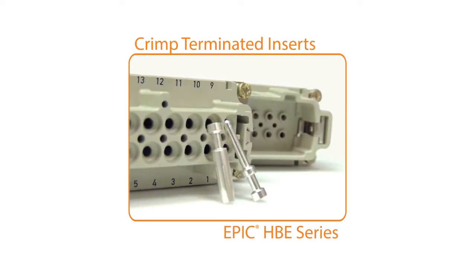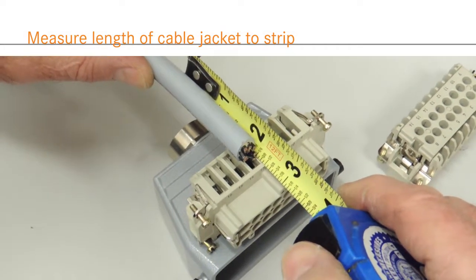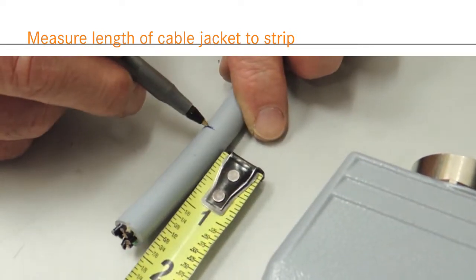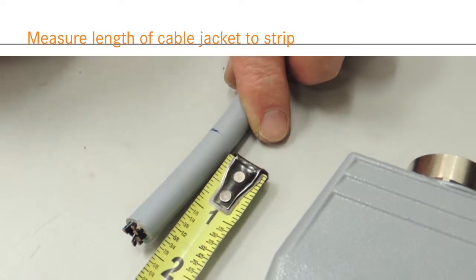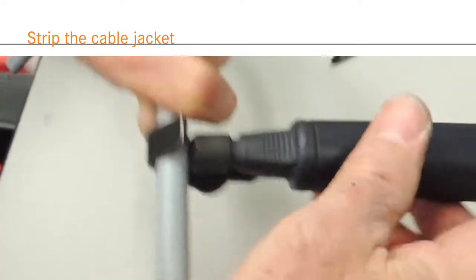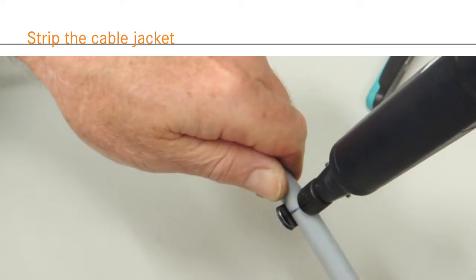First, we will look at wiring crimp inserts. As with every termination, first you must strip the cable jacket to allow you to easily terminate the individual conductors. The jacket should be stripped back enough to allow you to easily terminate the individual conductors, but not so much that the jacket is stripped past the hood's gland when assembled. For the housing shown here, 2 inches is a sufficient stripping length.